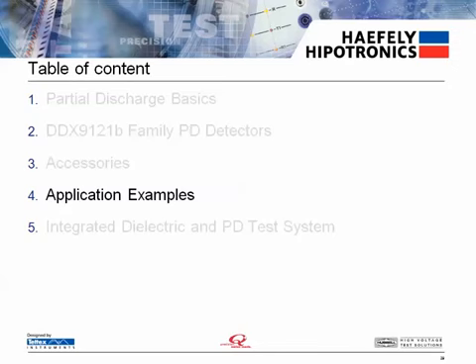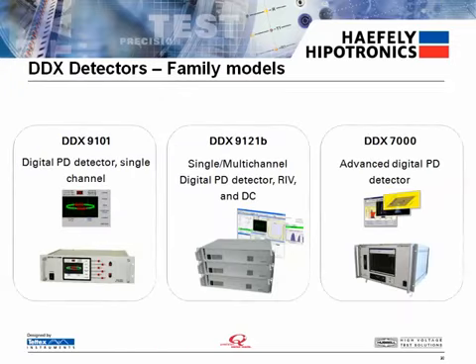Now for some examples to show what equipment we'll offer for specific applications. Here is the DDX family of partial discharge detectors. The 9101 is a basic single-channel detector ideal for pass-fail testing. The 9121B can be used for single or multi-channel applications, as well as DC and RIV testing. Finally, the 7000 is used for advanced applications such as cable testing and when additional analysis capabilities are required.